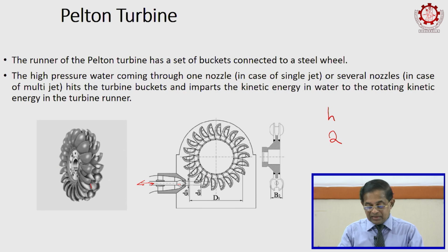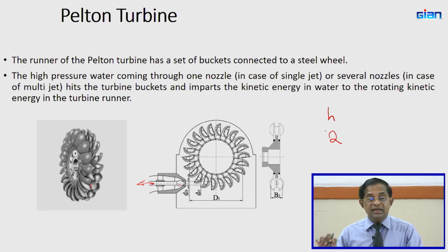Therefore, these turbines have to be manufactured, especially designed for this H and Q, right. So, you can't ask a hydropower turbine manufacturer, can you manufacture it in 2 months? He cannot. He has to first do a design and then manufacture it. So, they will take 6 to 9, 10 months for the manufacturing process, and then the generator also has to match the speed, number of poles, etc.